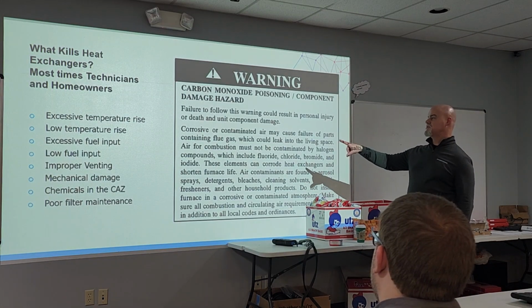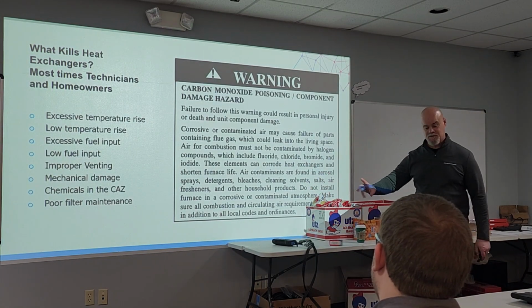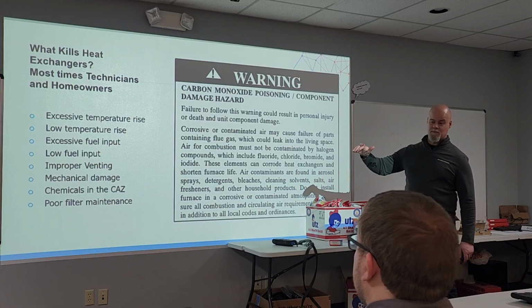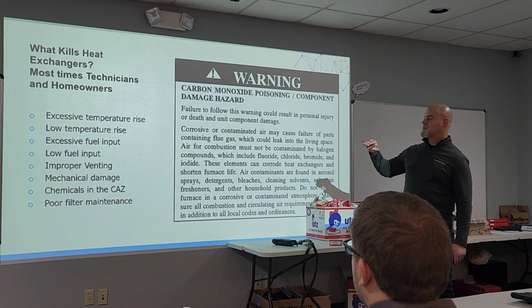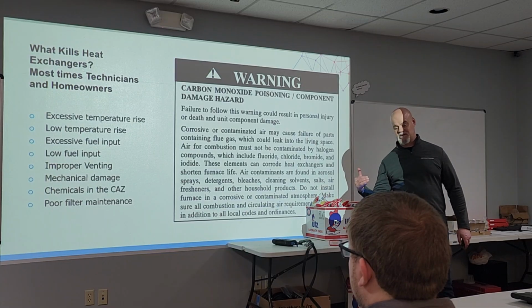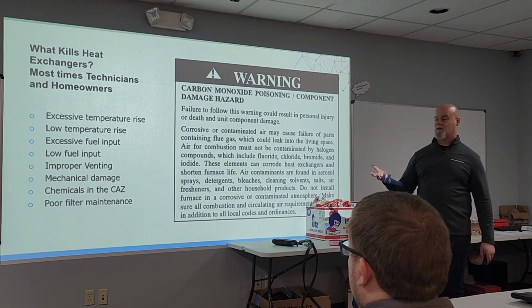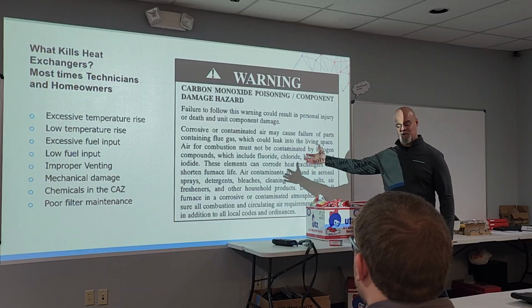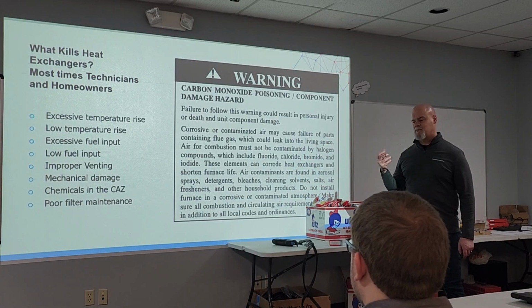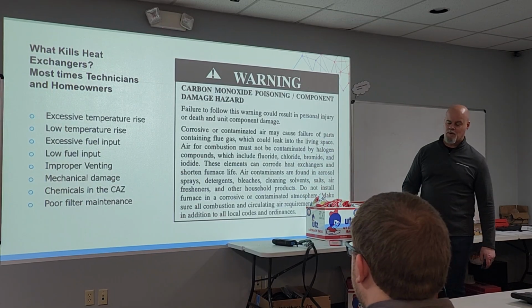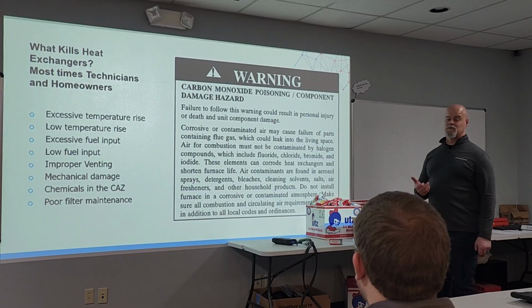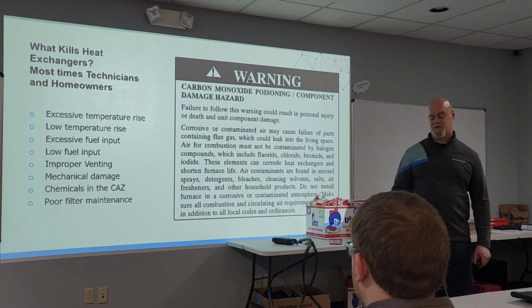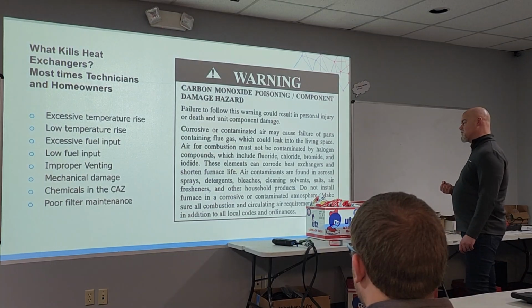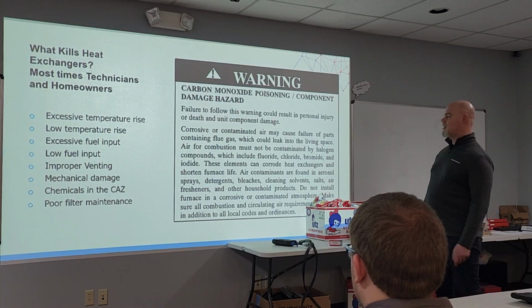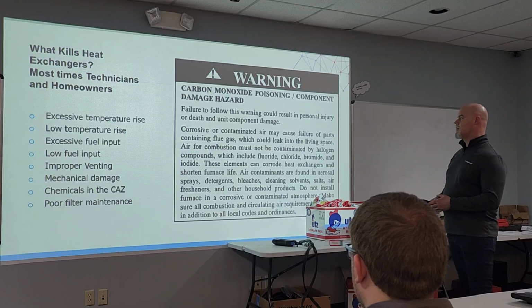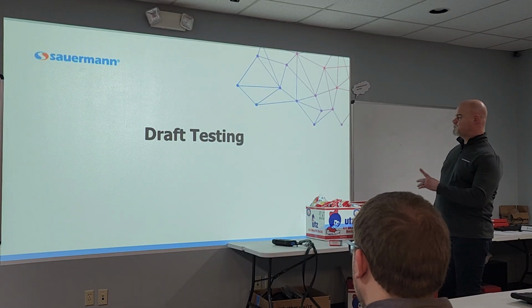Because what kills heat exchangers the most? You do, service technicians and homeowners. Excessive temperature rise, low temperature rise by not monitoring a system. Excessive fuel input, low fuel input, same thing. Improper venting, mechanical damage, but chemicals. That's where the homeowners contribute. The chemicals in that area. We want to keep those chemicals out of there or keep the bottles sealed. We don't want those things getting into that open air, especially with those older systems that are still using room air, those atmospheric systems, still pulling room air into that system. We don't want to have any improprieties in that air. So we want to make sure that we're monitoring that, okay?